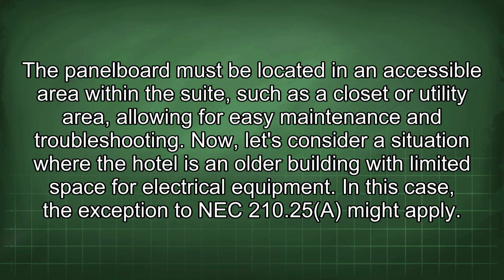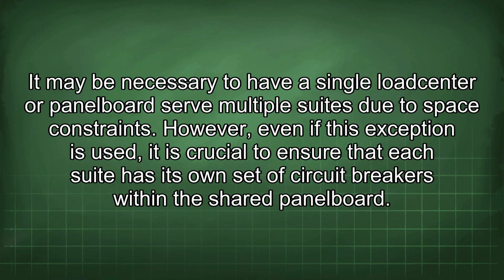Now, let's consider a situation where the hotel is an older building with limited space for electrical equipment. In this case, the exception to NEC 210.25 might apply. It may be necessary to have a single load center or panel board serve multiple suites due to space constraints. However, even if this exception is used, it is crucial to ensure that each suite has its own set of circuit breakers within the shared panel board.